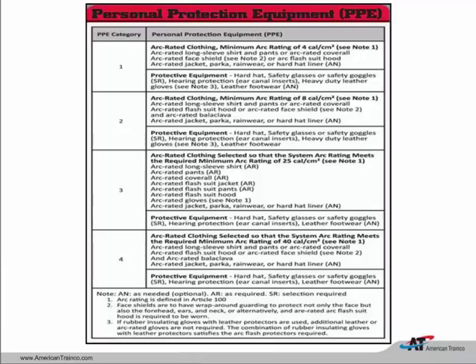This method applies when we walk up to a piece of equipment that has no label on it, or they used the PPE category method to generate the label originally. So PPE category 0, we don't see, it's gone. PPE category 1, very similar to 2012. Arc rated clothing with at least a 4-cal rating, long sleeve shirt, long pants. If we do go outside, we might need some rain gear. That's why we see in parentheses the letters AN, as needed. Also have to wear the hard hat, safety glasses. SR means select one or the other. So you're going to have to either wear glasses or goggles.